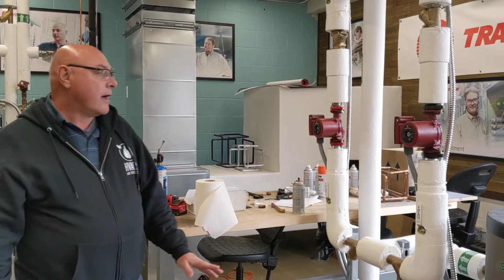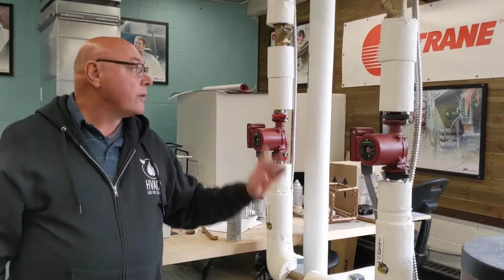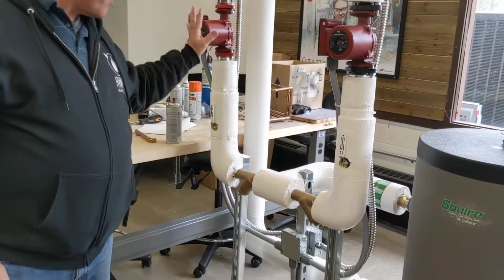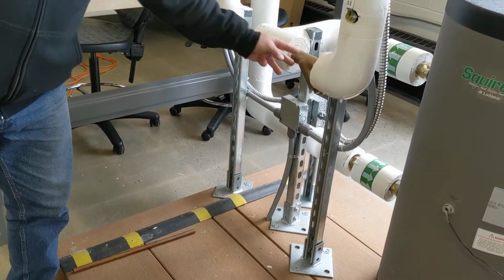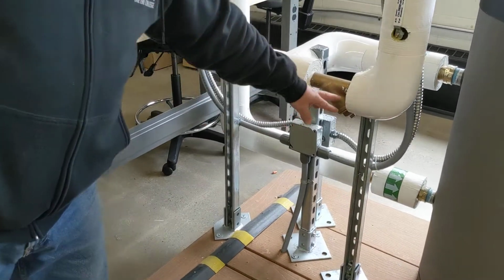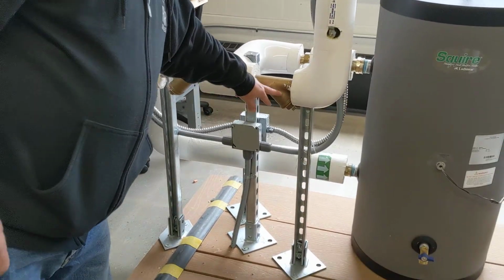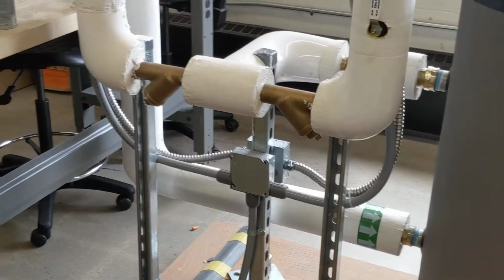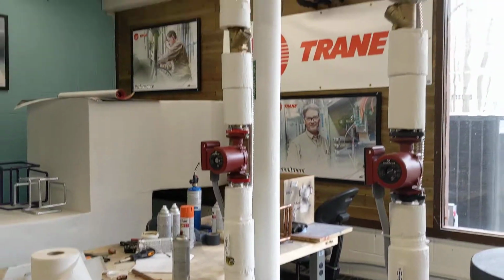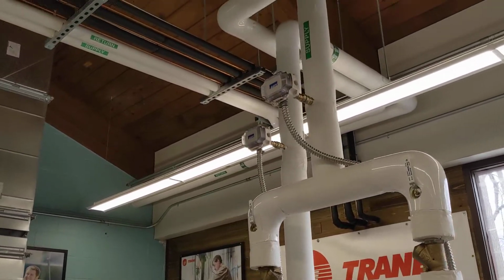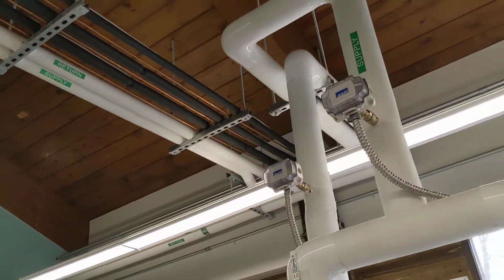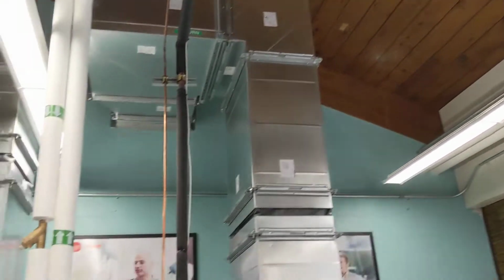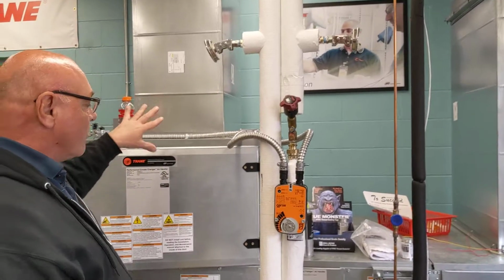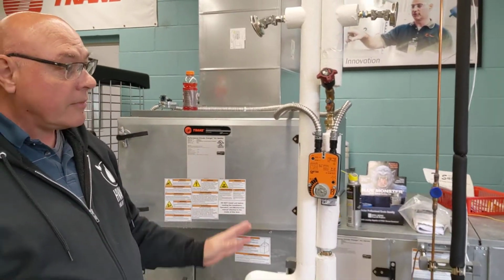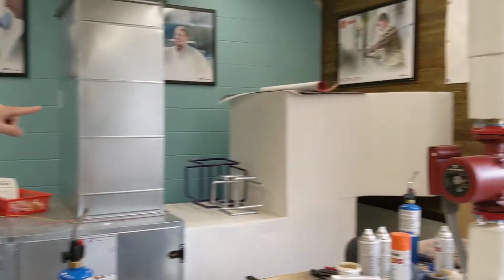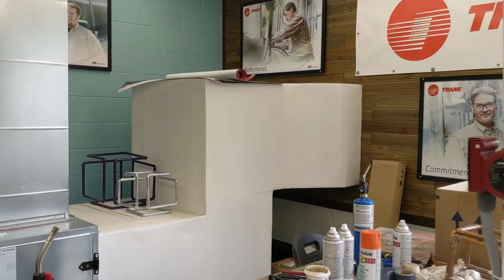a good thing. In our loop, we have flow switches, we have pumps, we have strainers that keep the water clean. If there's any dirt, it'll fill up in a strainer inside here. And you can see our piping going around, and it heads two directions. It heads through the wall, and then it also comes over, branches off, and comes to this unit here, which is an air handler.